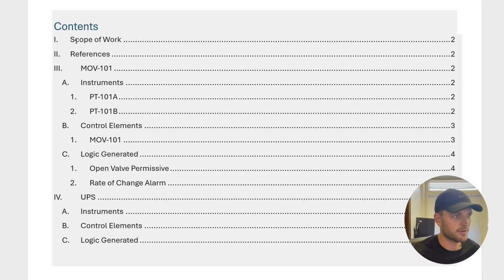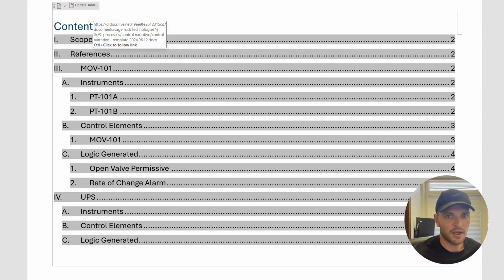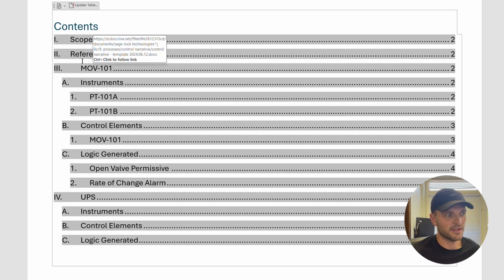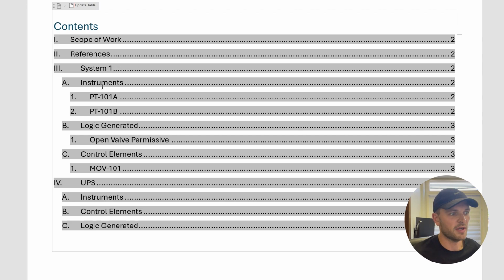So, how I like to set this up is I'll start with a scope of work and then I'll jump into references. So these are other documents that might need to be referenced. Typically, they help with checkout or with testing at the end. And then I do my sections by system. So in this case, we'll update our table. So we just have system one. And then, this could be like a pump unit that has inlet and outlet valves, maybe some pressure transmitters, suction and discharge, maybe a control valve, right? That would all be in that system. Sometimes for smaller facilities, you may only have one system, but sometimes you might have, we'll call it system one right here, which would just be an MOV with a couple pressure transmitters and then a UPS, right? So those are two kind of different systems that can interact, but I like to break it down that way so they're tested independently.